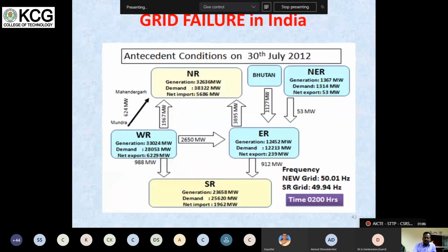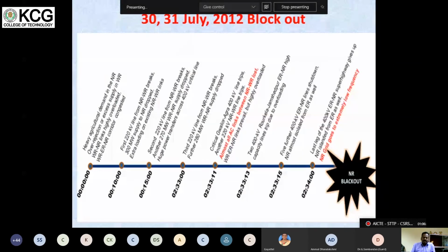Coming back to this system, what is happening? You can see the figure now. What happened on the 30th? Heavy load was happening in the northern region. That is what we already said. The discipline should be maintained by the grid managers or utilities. Whatever the allotment is, that power only they should draw. If they draw more power from the grid, then it leads to grid failure.